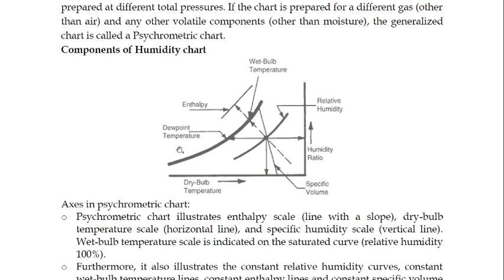Similarly, you can see a curvature on the temperature. That is the wet bulb temperature line. In fact, the dew point value is also mentioned on that. So it will be a slant line, something like this. Then you have values of enthalpy, humidity ratio, and relative humidity. Relative humidity lines are curves almost parallel to the temperature lines. Then the humidity ratio is the y-axis over here, and you have specific volume lines coming over here, and maybe at the bottom you can get those values.